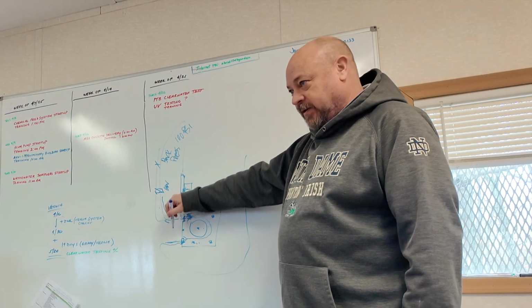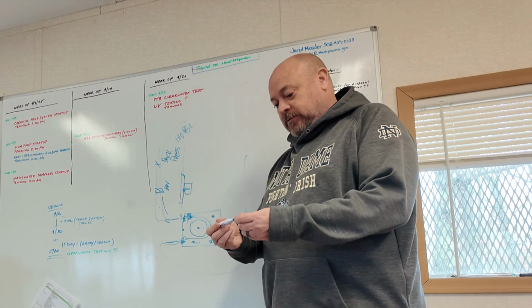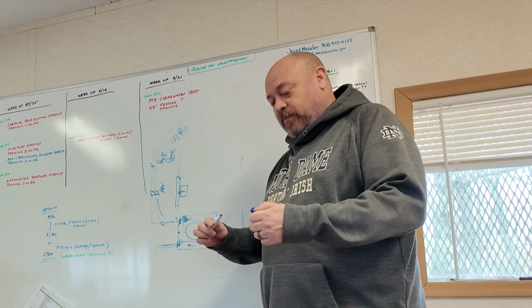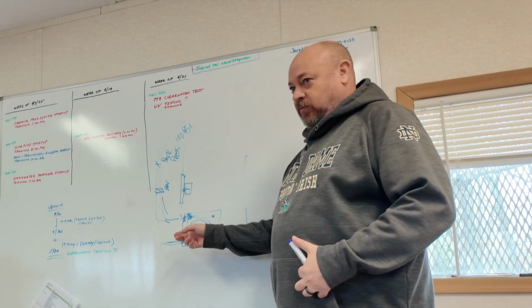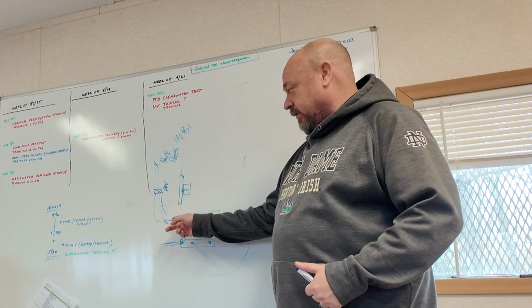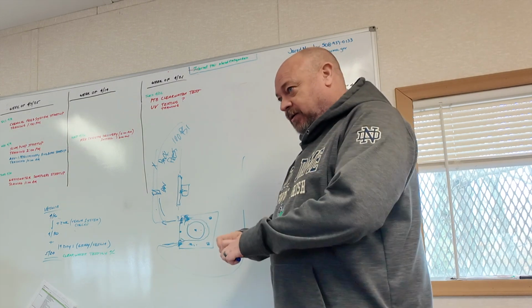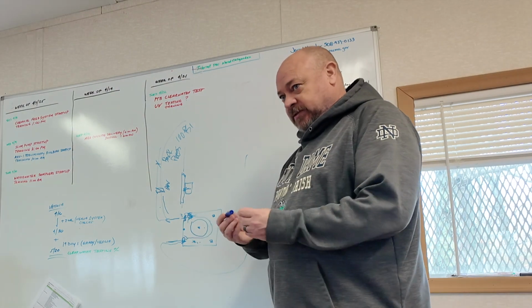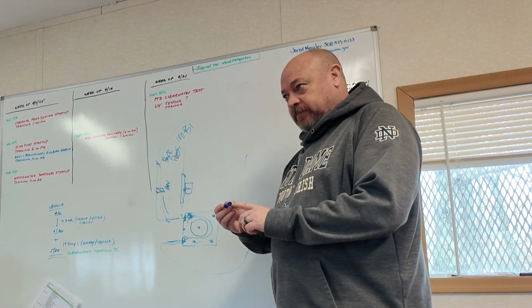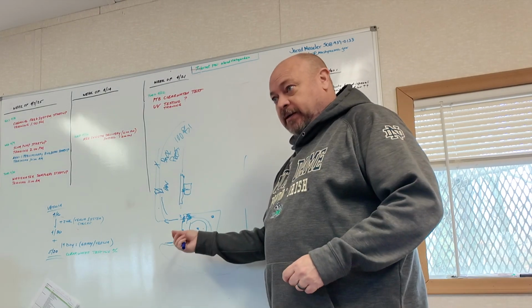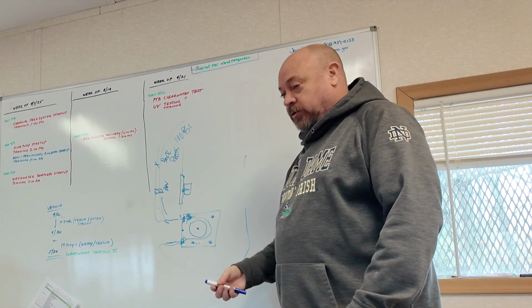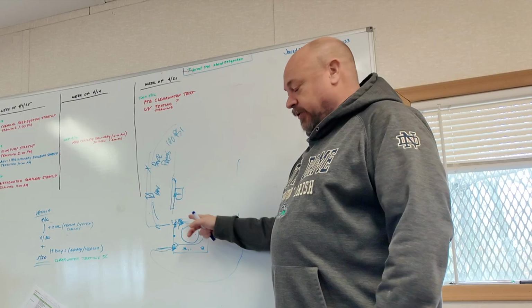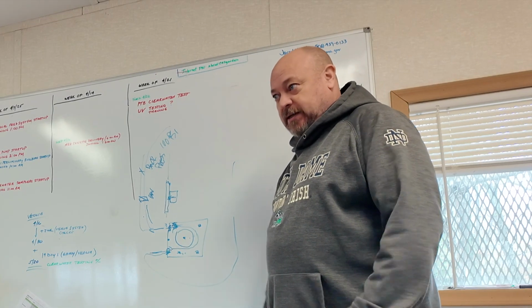They have quick connect fittings. So basically you lock them in place and you pop them up. What's nice about that is you get a call in the middle of the night. You don't have to worry about cracking union threads or anything like that. You just pop it in, pop it off. The tube comes as an assembly with the other side of the quick connect on it. So all you do is put a new tube in, pop it back into place, prime the pump, and away you go. You don't have to worry about priming the pump because there's no ball check, so it's basically self-priming by nature of the pump.